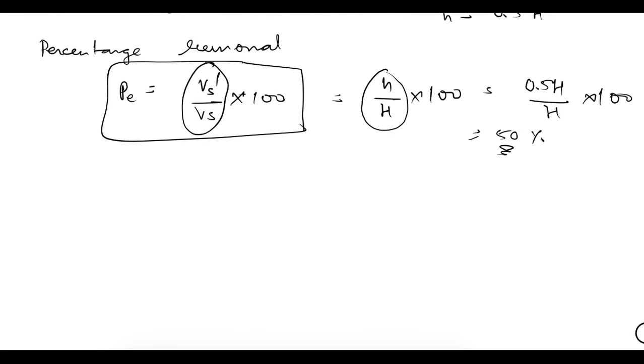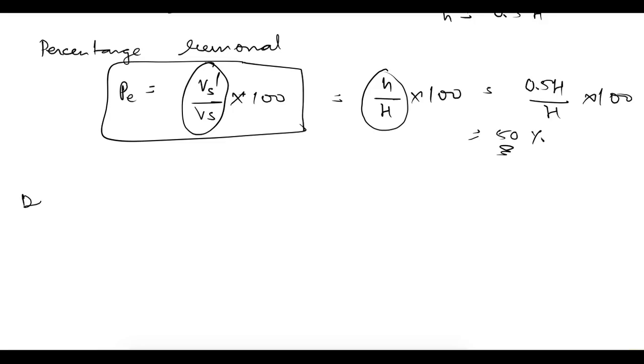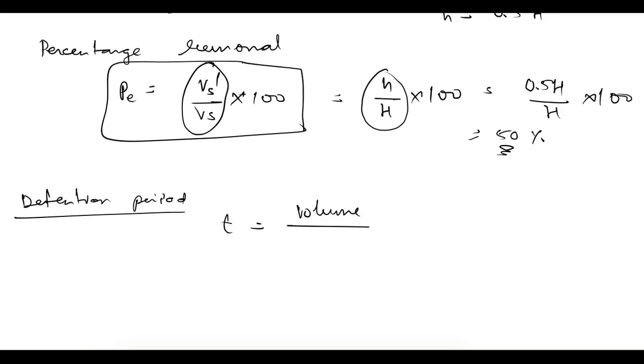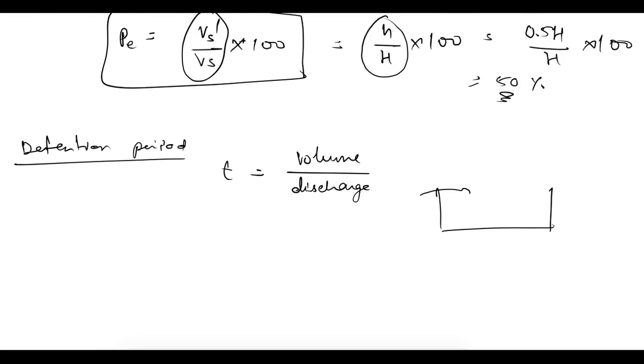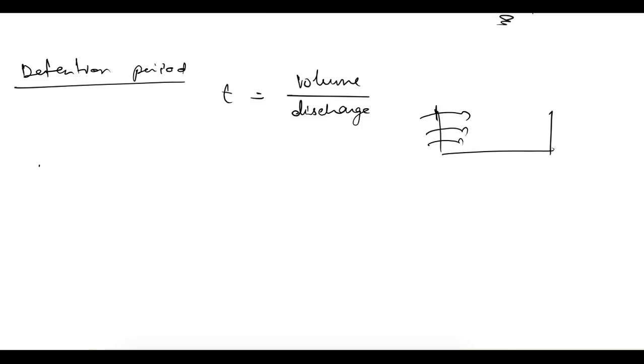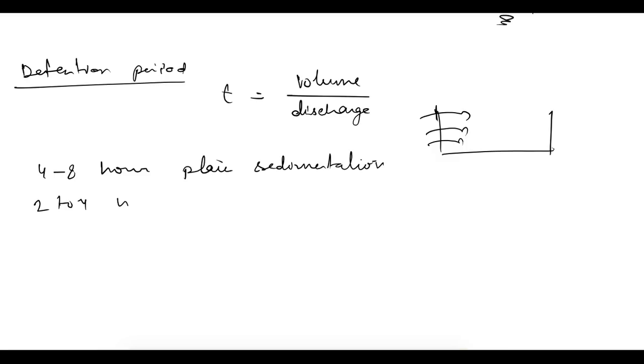After that, there are some additional concepts. Retention period is simply Volume / Discharge — it means how much time the water is kept in the tank. The retention period for a plain sedimentation tank should be between 4 to 8 hours, and for sedimentation with coagulation it is 2 to 4 hours.